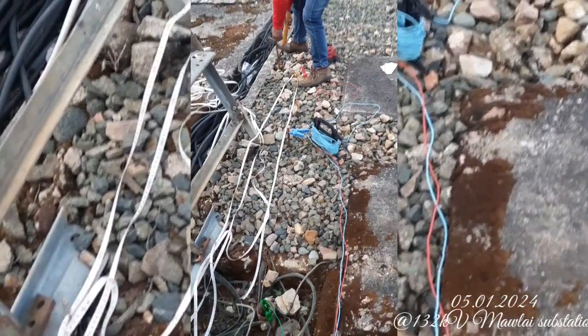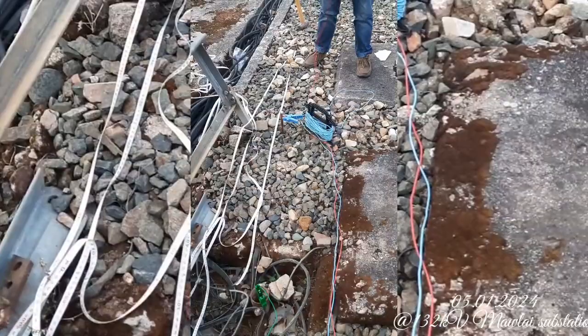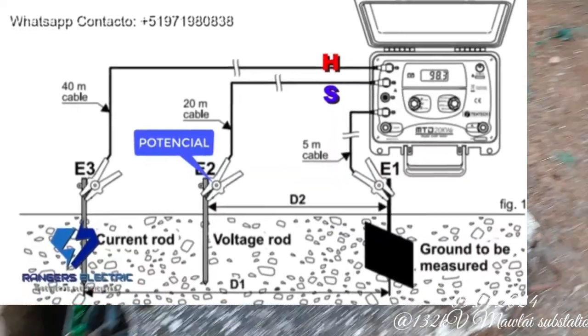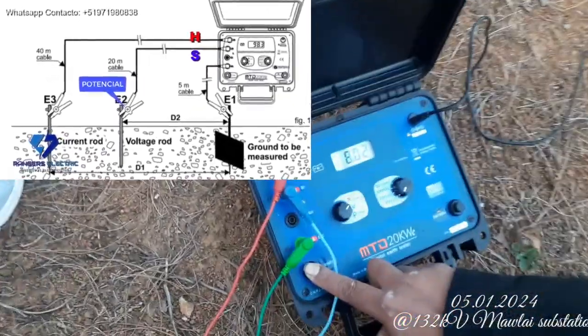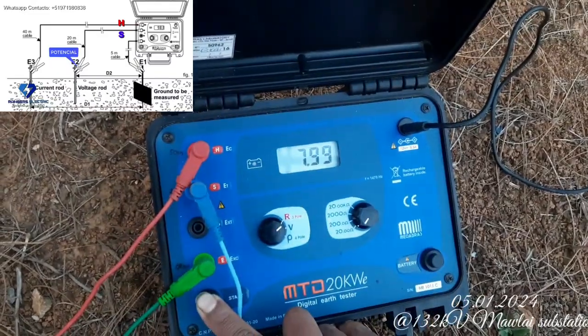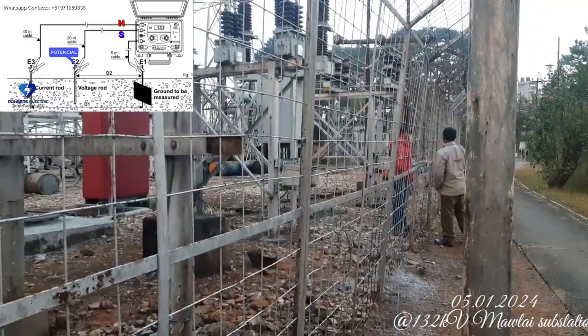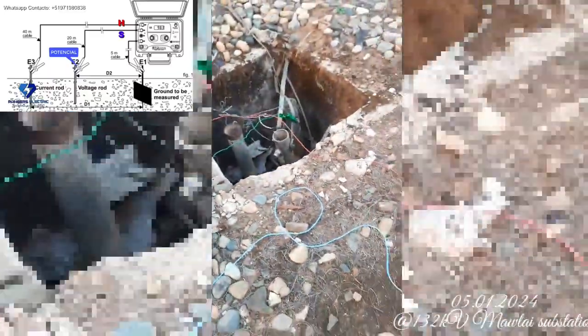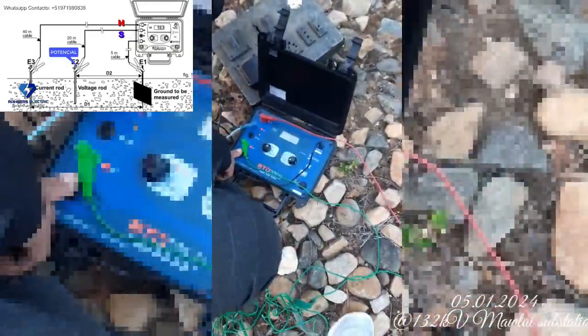So we will keep on reducing our distance to the standard setup. When you have to measure the resistance, the instrument has to be connected like this: your voltage electrode cable has to be placed at a distance of 1 meter from the center point of the earthing pit under measurement. Keep it at 1 meter, then in a straight line insert your current rod, the red one, at twice the distance, so the current rod should be at 2 meters while the voltage rod is at 1 meter. This is the standard distance, and it's also done this way by MRT people when they perform resistance measurements.